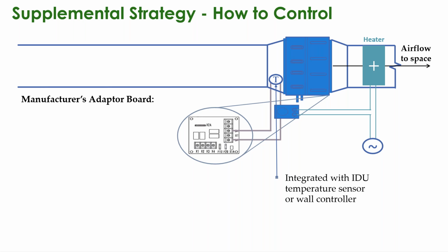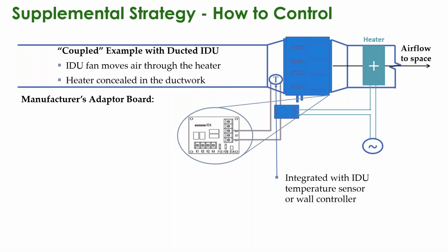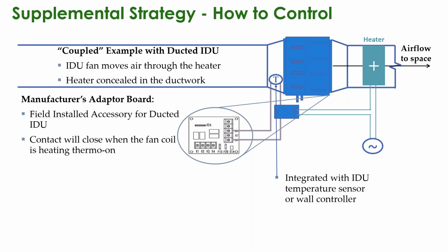So how does this get controlled? It varies by manufacturer, but in the example of a ducted indoor unit, the ducted indoor unit would be the source that's moving air through the heater, whether that be an electric resistance heater added into the ductwork, a hot water coil, gas heater, etc. Typically, you're going to have a manufacturer's board that operates based off of logic on the unit that is going to allow contact closure when the fan coil is in heating thermo-on, which means there's an active heat mode.